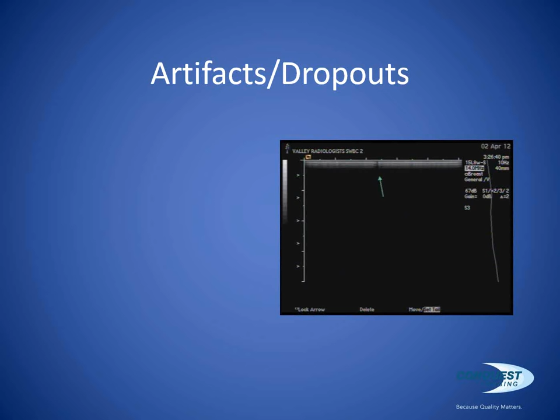You can see that slight artifact in the near field of the probe. We need to start looking at, what is this? Is this caused by the actual array of the transducer? Is it the cable? One of the things that we do, it's a field test, but you can take a metallic object. I like to use a ballpoint pen. I carry a pen that's made out of metal that I can roll across the face of a transducer. A paper clip works very well.